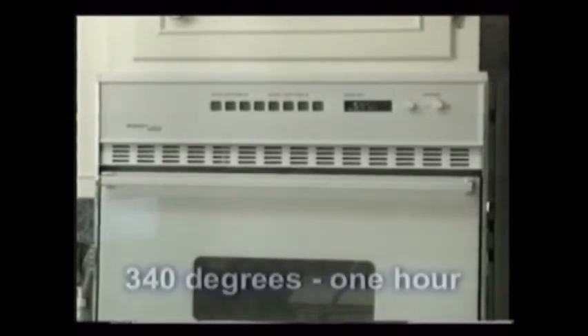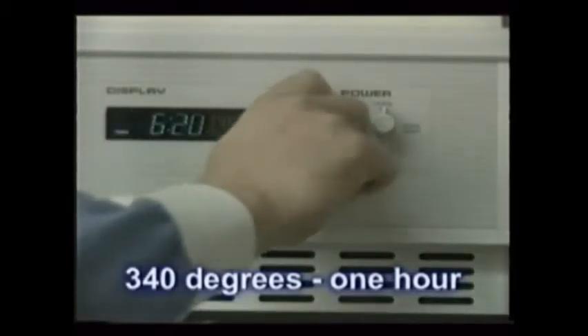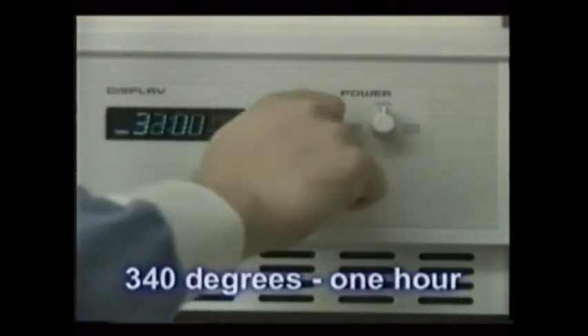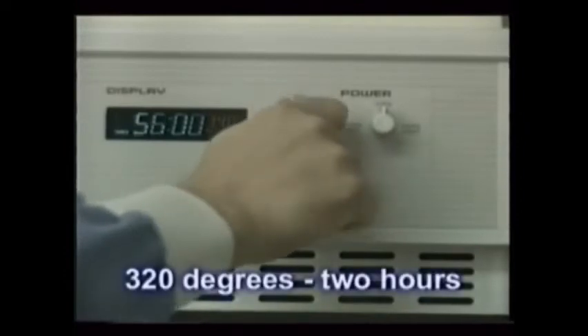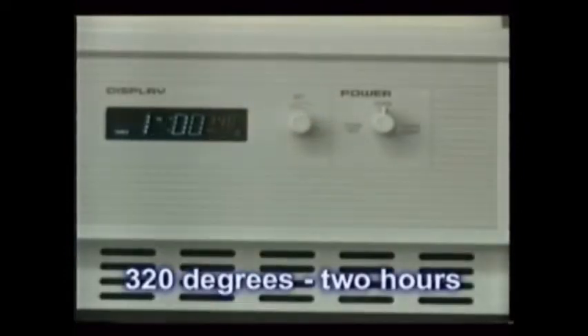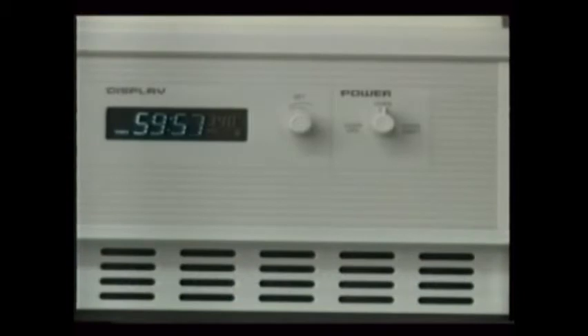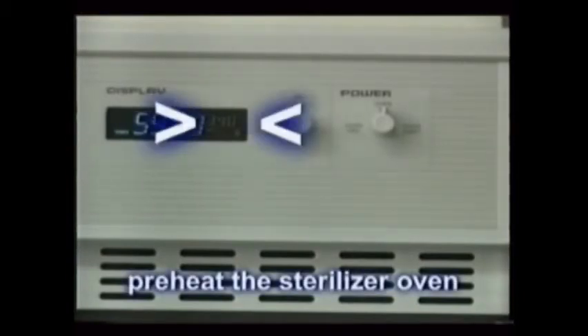Using a thermometer and a timer to monitor the process, heat the properly prepared, foil-wrapped items to 340 degrees for 1 hour or 320 degrees for 2 hours. Increase the time if the packaging or the loads are large. It's preferable to preheat the sterilizer to the operating temperature before you insert the items. Remember to use the indicator tape to later remind you that the package has been through the sterilization process.